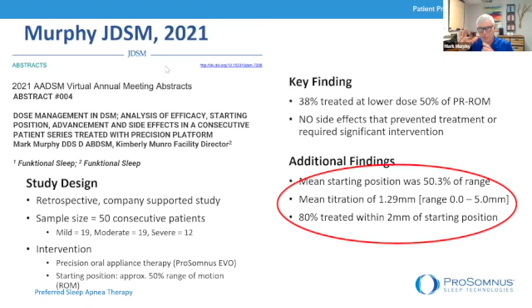Now, if you look in the literature, historically, all those other studies we're talking about, most of the guidelines from most of the manufacturers will talk about starting patients at 65, 70, 75, or 80% of their range of motion. And you would have to, if you had a bulkier device, if you had trouble stabilizing the mandible and you were going to lose 1.8 millimeters of advancement with 5 millimeters of opening because it was a 70-degree post on the dorsal, that's the math. It's just simple geometry. But if you're going to lose 1.8 millimeters, you'd have to advance that patient another 1.8 or 2 millimeters to accommodate that if they happen to sleep with their mouth open. So these were things that led to challenges with adherence, challenges with more side effects, challenges with trying to maintain the same bite, things like this. So this lower dose, better efficacy, everything is kind of these different puzzle pieces all working together to make something work a little bit better.